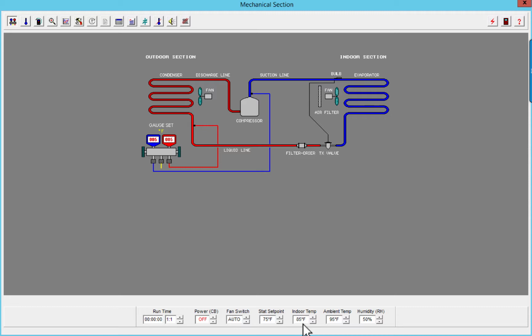Now, you've probably heard me say this before, but I am really concerned not about pressures, but I'm more concerned about temperatures when I'm looking at the refrigeration system. My gauges that display pressures are only a tool for me to find out what the temperature of the evaporator and the condenser is. So my high side gauge shows me the pressures that are the same any place through the high side of the system between the compressor and the metering device.